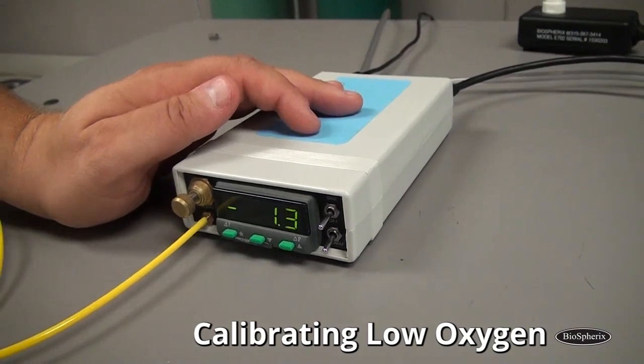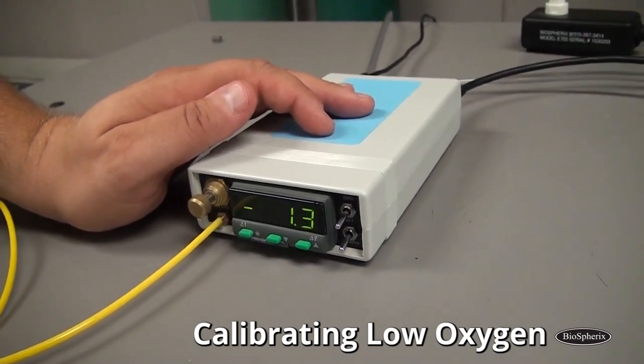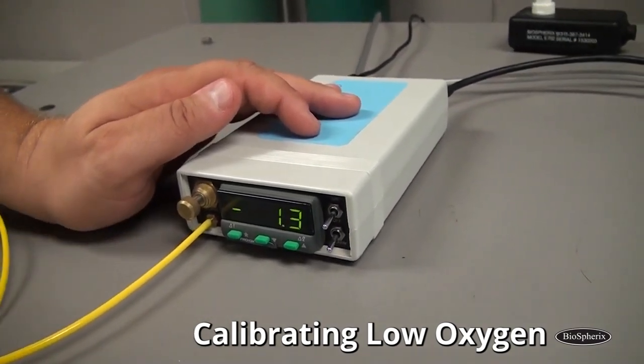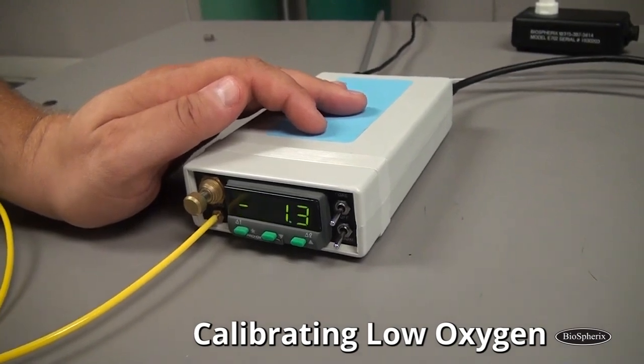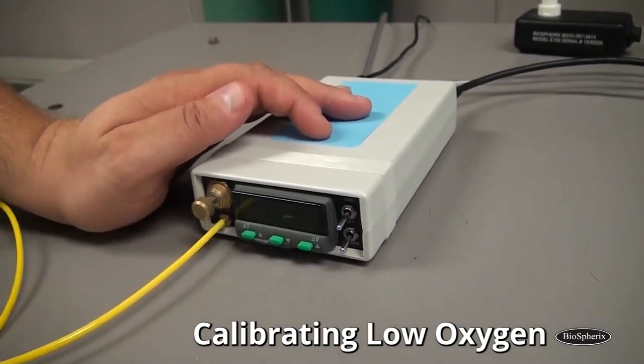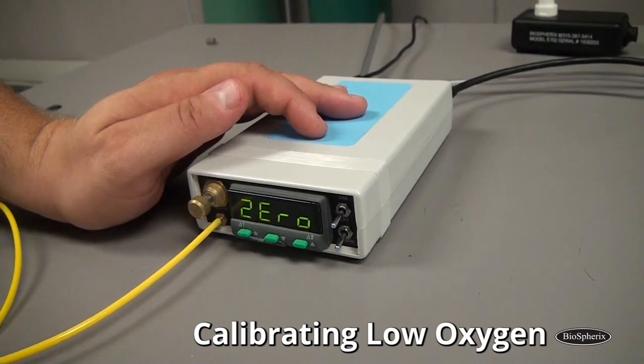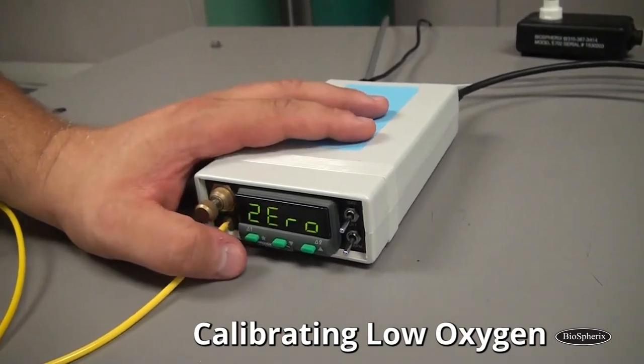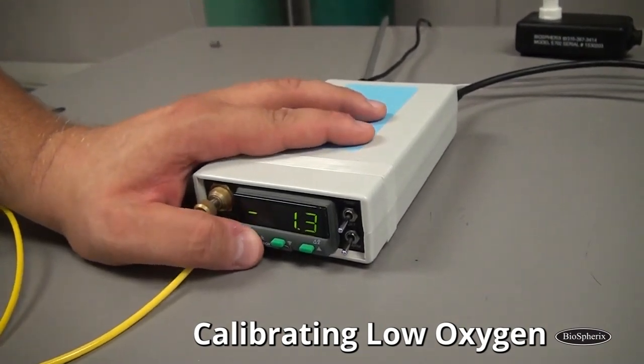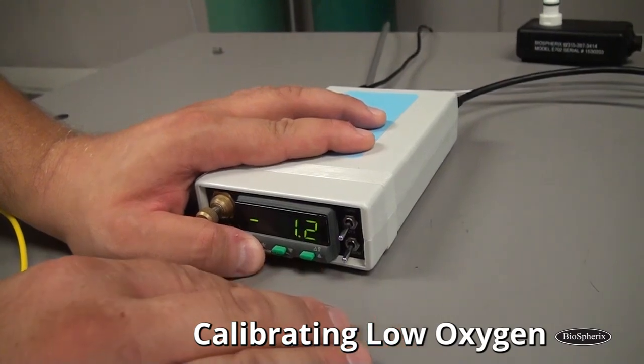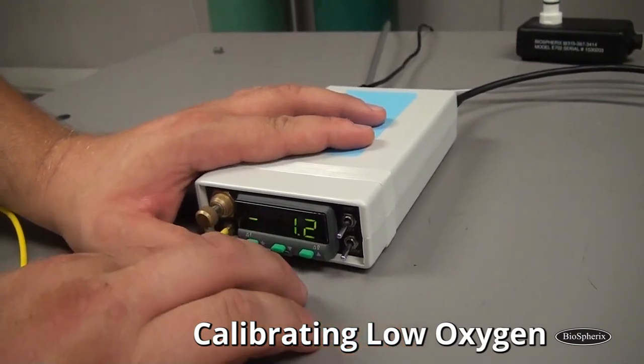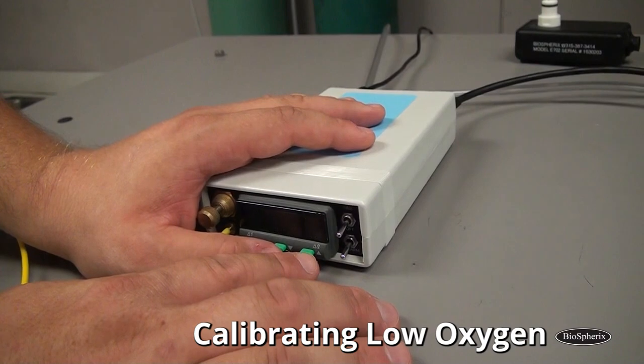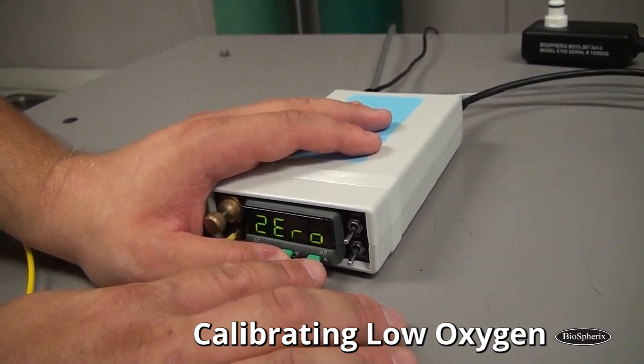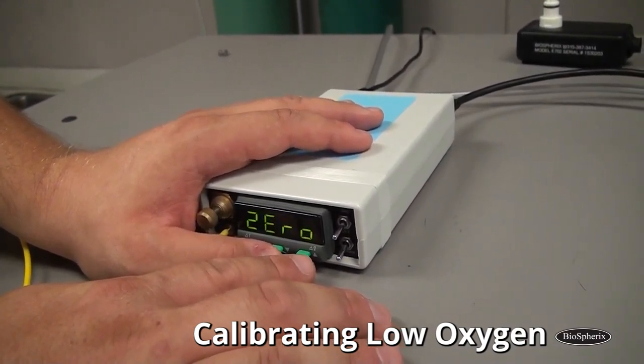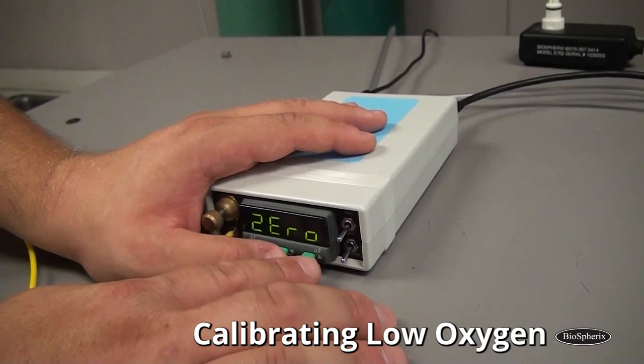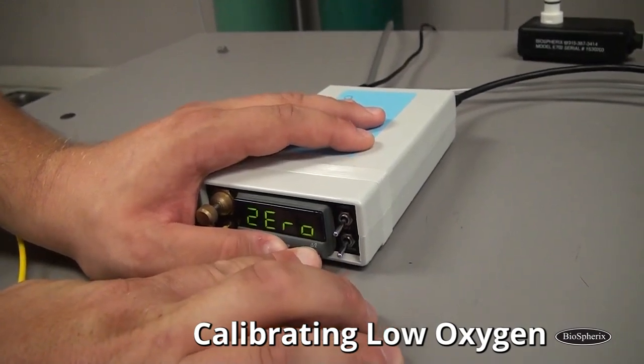So we were minus 0.1, which means we were 0.1 below where we need to be. So we have to do the opposite to this coefficient. So we need to raise it by 0.1. So I'm going to hold the star, press up once, and then I'm going to save it and exit the program mode, and do that just like you entered. You hold the up and down for 3 seconds.